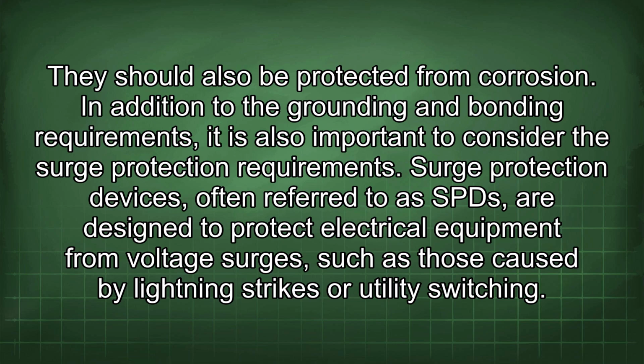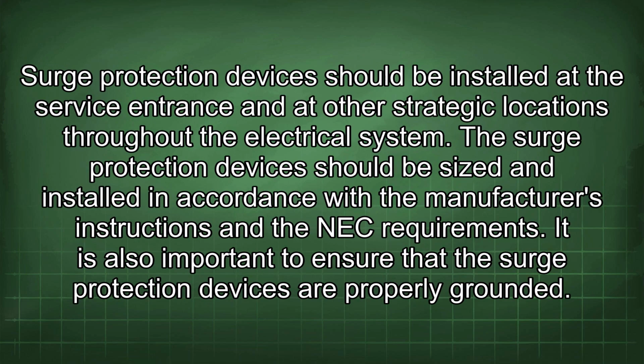In addition to the grounding and bonding requirements, it is also important to consider the surge protection requirements. Surge protection devices, often referred to as SPD, are designed to protect electrical equipment from voltage surges, such as those caused by lightning strikes or utility switching. Surge protection devices should be installed at the service entrance and other strategic locations throughout the electrical system. They should be sized and installed in accordance with the manufacturer's instructions and the NEC requirements.